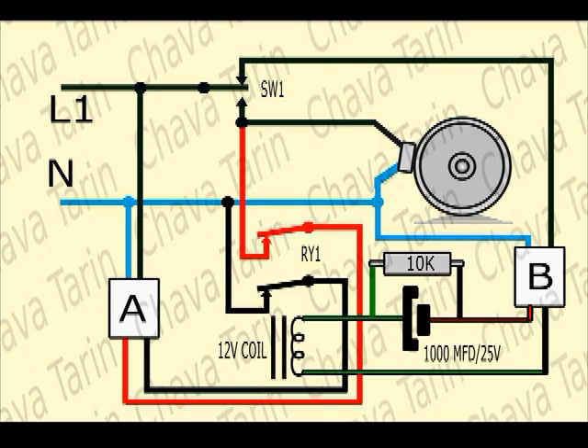The relay delivers 12 volts or so from the braking power supply labeled A. If this power supply is strong enough, it will force a braking current through the low-resistance motor stator windings.